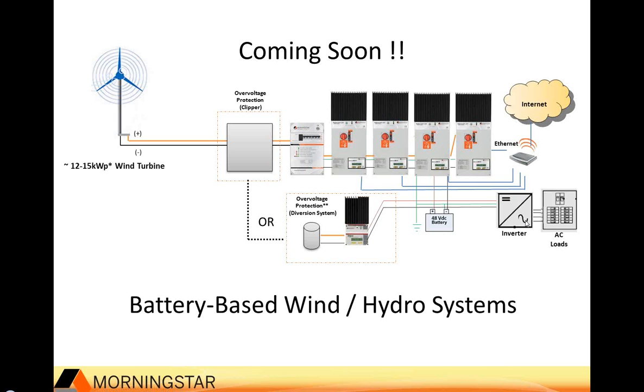It allows you to use your grid tie system for a lot more than just sitting there unused during an anti-islanding condition. During this time, you can charge a battery. You can then use an off-grid inverter, such as this one, of any size, to provide backup for your loads. So it's a little bit different way of looking at backup, and it's available because we have a 600 volt input on our charge controller. Offering that DC transfer switch will enable this. It's being designed so that you could use several of our charge controllers. I think the current maximum amperage we're looking at now is about 100 on the input. Since we have 15 amp inputs to each of the controllers, that would easily give you up to 4 of them that could be used to transfer a very large array over and charge an off-grid battery bank.